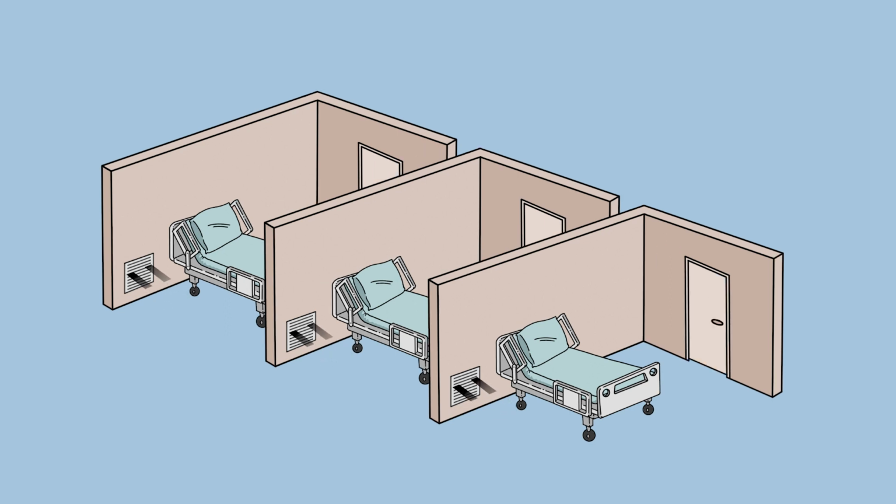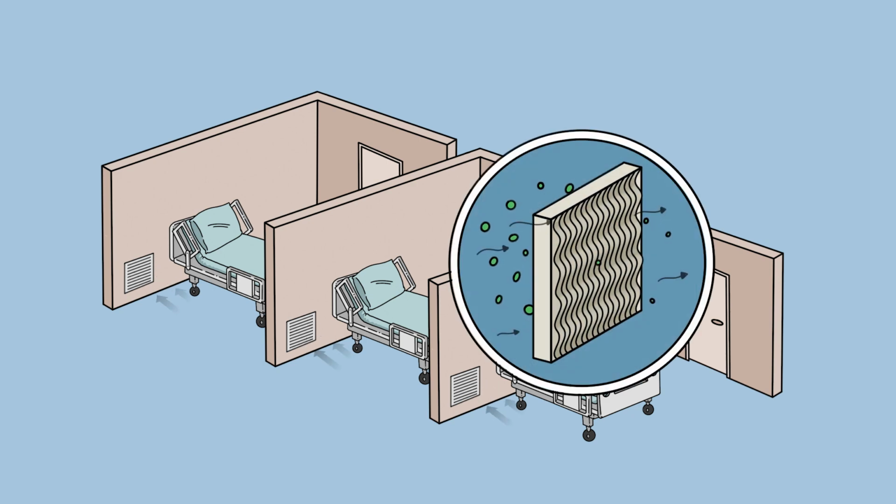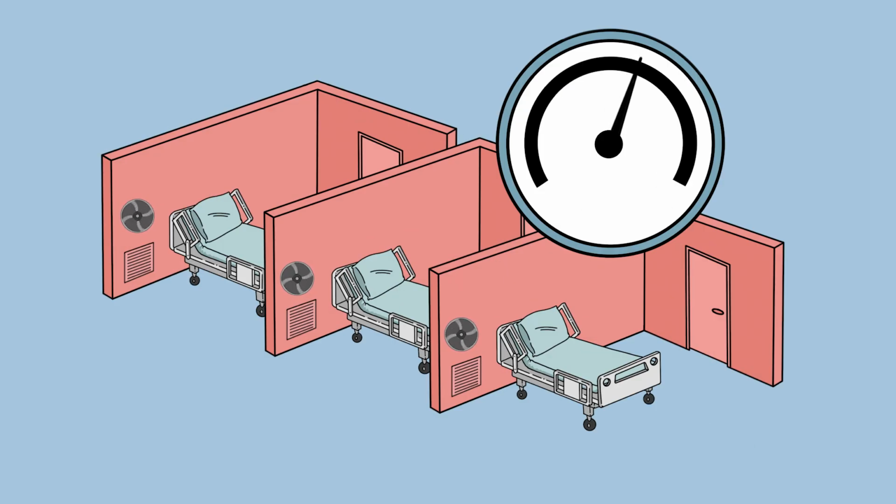As outlined in the ASHE guidelines, in these situations, you will want to consider the third best option, pulling the air out of the room and exhausting it through a HEPA filter into the building's HVAC return ductwork with a positive pressure fan. However, there are several reasons this is one of the least favorable options for retrofitting an area to negative pressure. Ducted HVAC systems have fans that are sized for the supply and return requirements of the spaces they serve. Adding a positive pressure fan in a room and tying it into the room's HVAC return ductwork increases the airflow and pressure. This can change the air balance of the entire system, including at the individual room level.